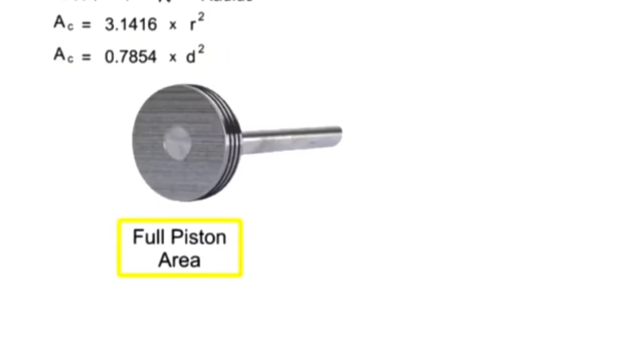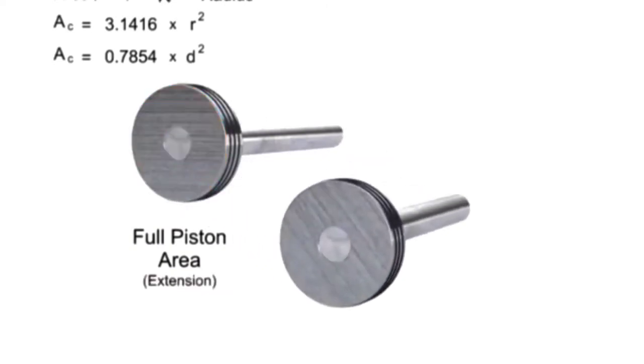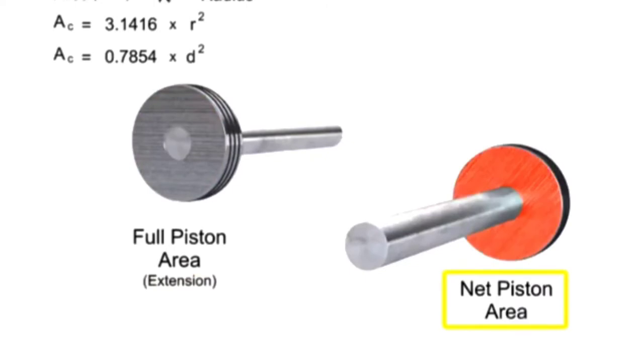The full piston area is the side of the piston without the rod. This is the area that sees pressure as the piston extends. The other side of the piston is called the net area. This area is the size of the full piston area minus the area of the rod. The net area feels pressure when the cylinder retracts.